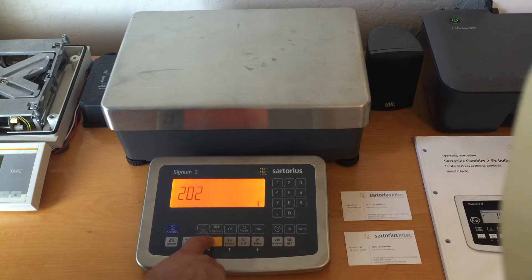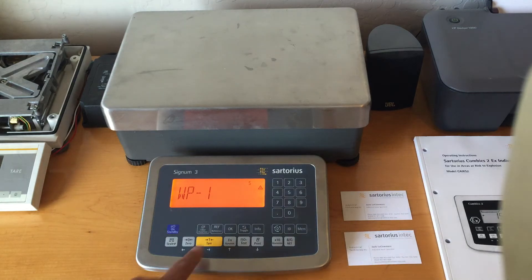2-0-2-1-2-2 is the service password. Press the tare key one more time and you'll see a flashing cursor. Back out just one level, then press and release the function key until you see WP1. Press and hold the tare key until it goes mostly blank, then let go.